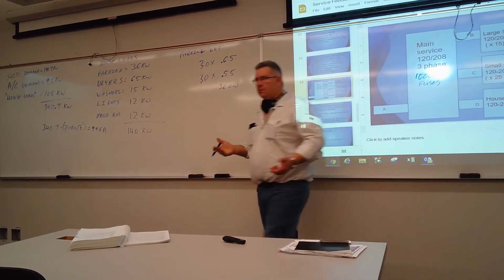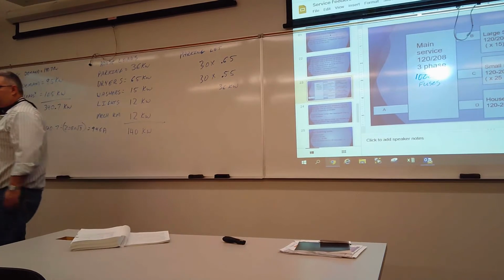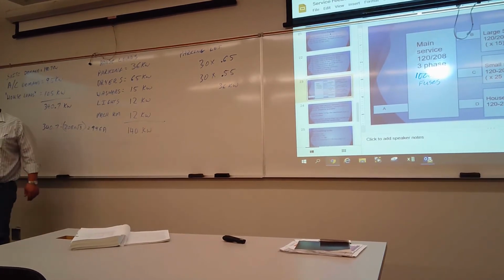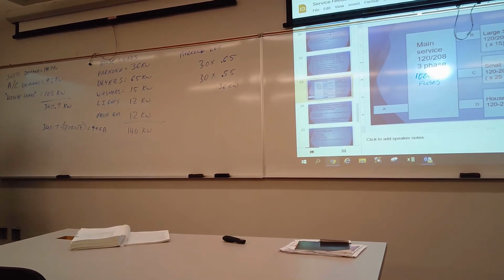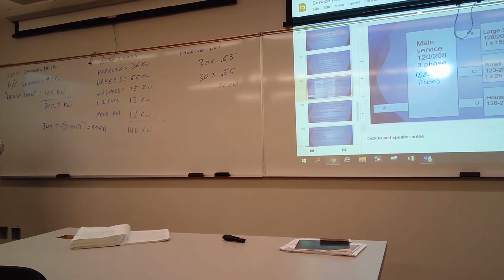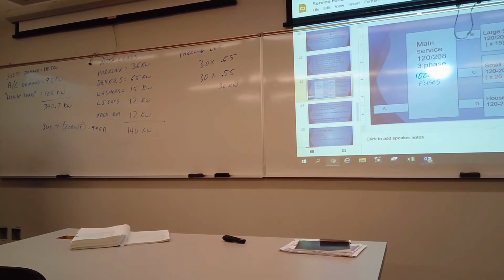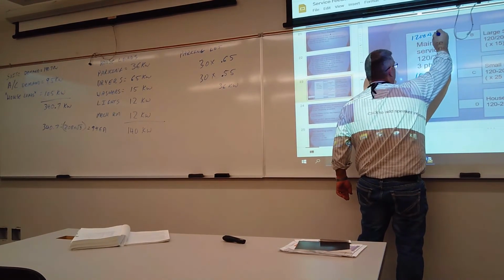Remember where the rule is for standard disconnects? Table 13 gives you standard fuses, and your standard disconnect size. You just have to write down and remember: 30, 60, 100, 200, 400, 800, 1,200, 1,600, 2,000, 3,000, 4,000. So you're going to have 1,000 amp fuses, and this will be a 1,200 amp rated switch.